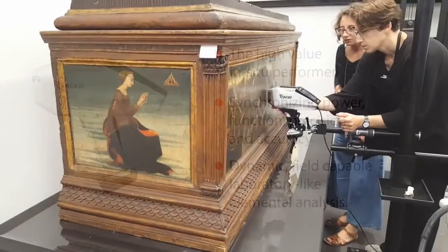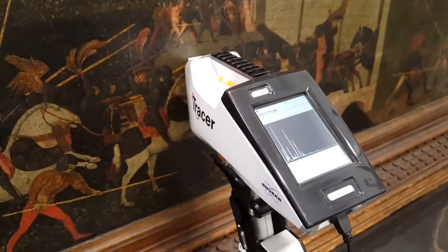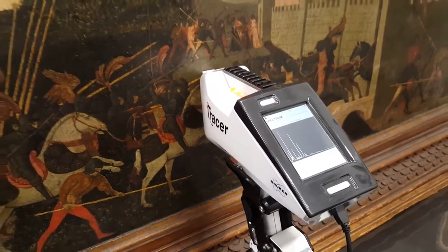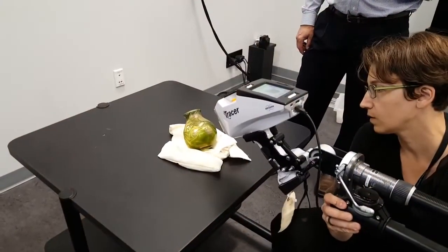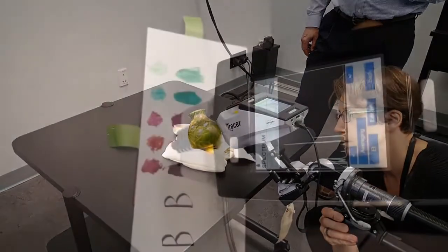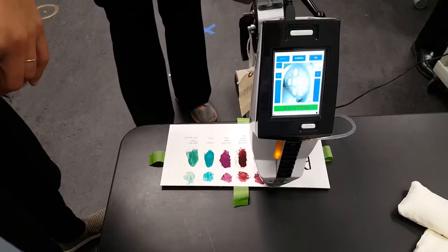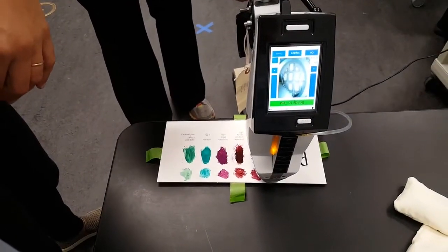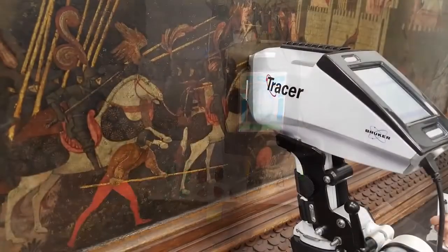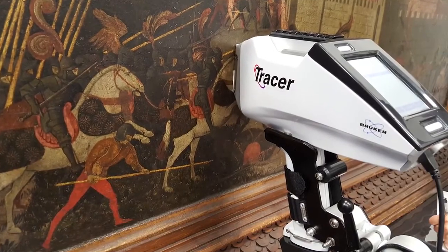For cultural heritage conservators, delivering a laboratory-like portable XRF analyzer able to perform complex evaluations of multi-faceted materials without harming a valuable sample is critical. They require an analyzer to help ensure appropriate preservation treatments or to authenticate objects. The Tracer 5i's internal camera with reticle alignment helps select the sample area quickly and store up to five enhanced resolution photos per assay to record the sample spot analyzed.